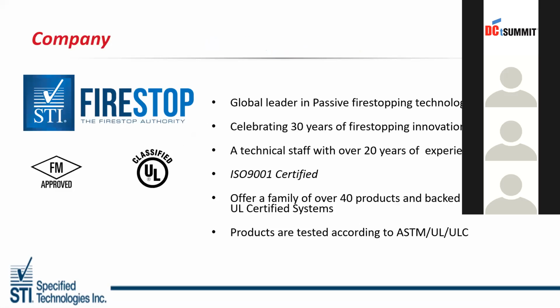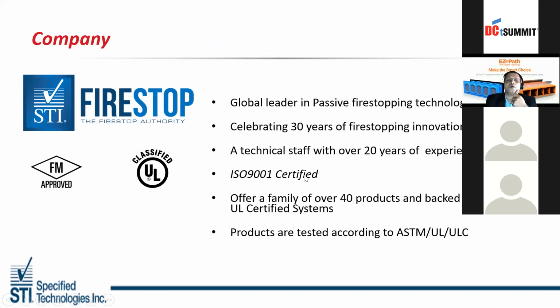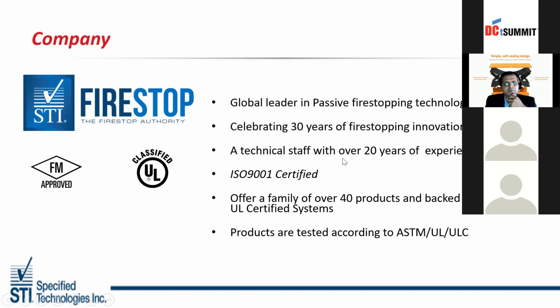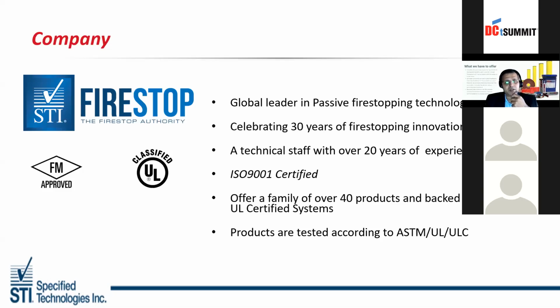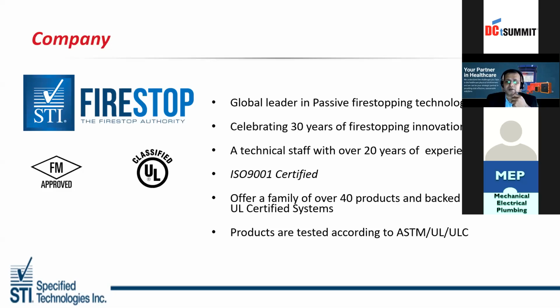STI is, as I mentioned, a US based company, and we have completed 30 years of innovation. We have technical staff to support you for the projects wherever required, the EJs, engineering support, whatever is there. It's an ISO 9001 certified company. We have almost 40 products backed up with 1300 UL tested systems. Only having a product is not sufficient, but the UL tested systems are the most important part in any fire stopping product. And all the products are tested as per the ASTM E814 and UL 1479 standards.